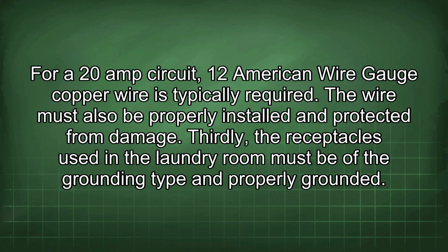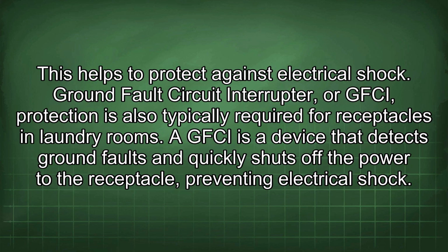Thirdly, the receptacles used in the laundry room must be of the grounding type and properly grounded. This helps to protect against electrical shock. Ground fault circuit interrupter, or GFCI, protection is also typically required for receptacles in laundry rooms. A GFCI is a device that detects ground faults and quickly shuts off the power to the receptacle, preventing electrical shock.